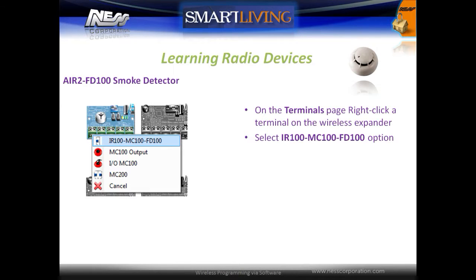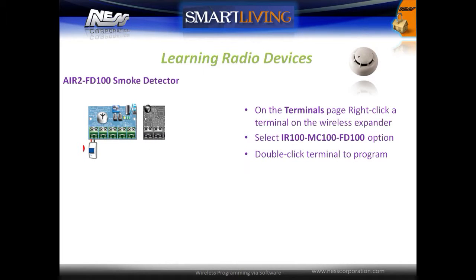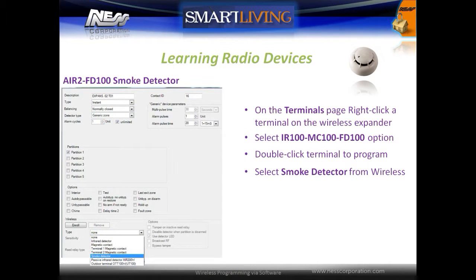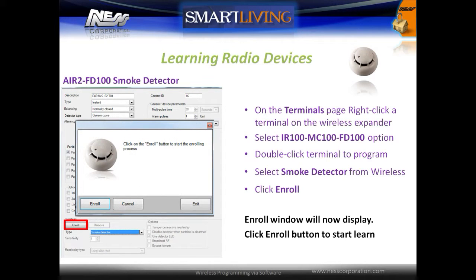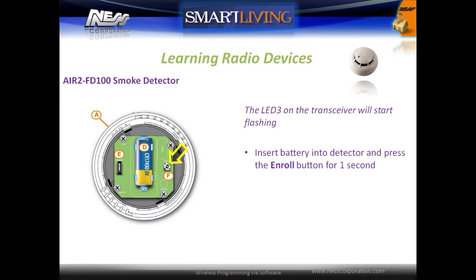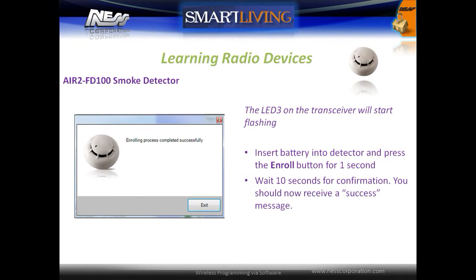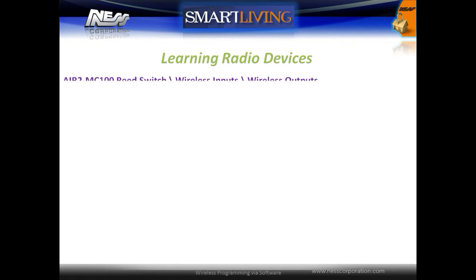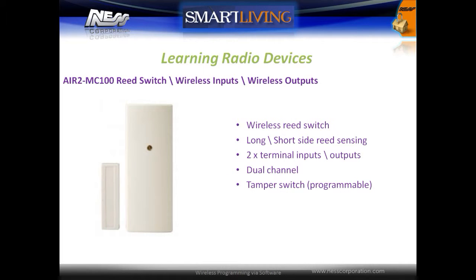On the terminals page, right click on a terminal on the wireless expander to enroll the sensor into, and select the IR100 option. Double click the terminal to open the programming window. Under the wireless programming section, select the type as smoke detector. Click the enroll button to enroll the detector. Once the system is in enroll mode, the transceiver's LED 3 will start to flash — press the enroll button on the device. After about 10 seconds, a message should confirm that the device was enrolled successfully.